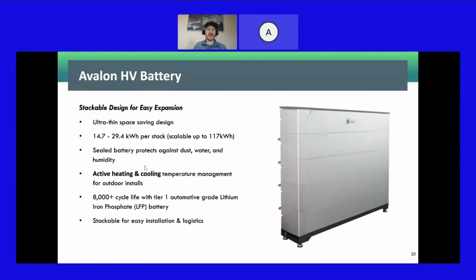Each battery module is a sealed battery, so it protects against dust, water, and humidity, has active heating and passive cooling management, and an 8,000 cycle life, and it's stackable. Basically you put the floor plate down on the ground, and then you stack each battery unit, and you can see these end caps. They come off, and that's where the battery connections are. Each battery weighs about 90 pounds, so installation is very simple and very quick, just stacking the different battery modules.